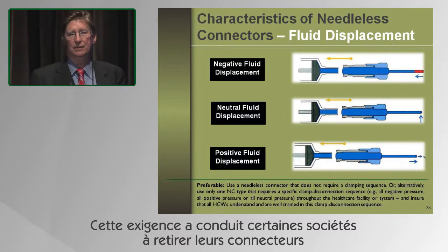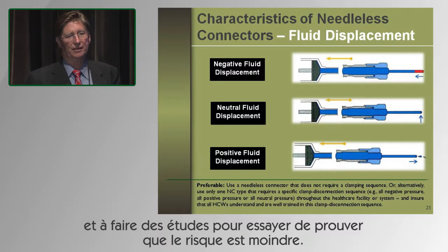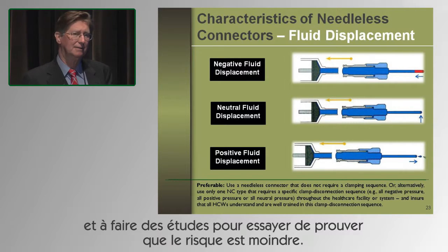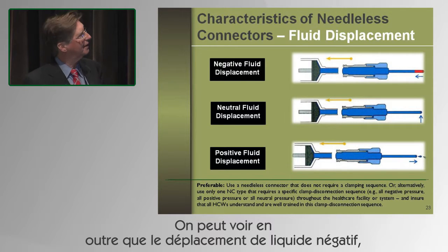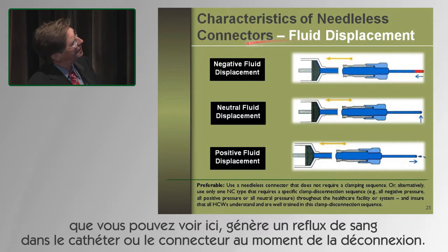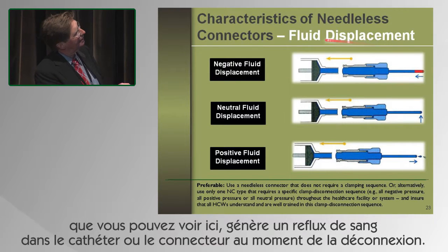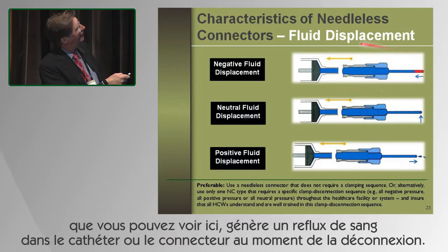That led to a number of companies withdrawing their connector from the marketplace, and 2 of the companies to do studies to try to document that the risk was less. But it led to a further understanding that the fluid displacement, such as negative displacement, as you can see here, when you disconnect, you get blood flow back into the either catheter or connector.